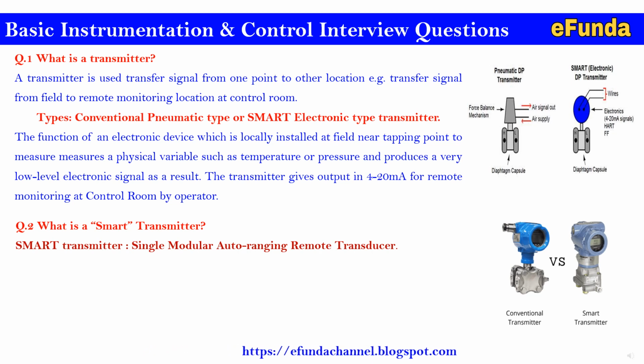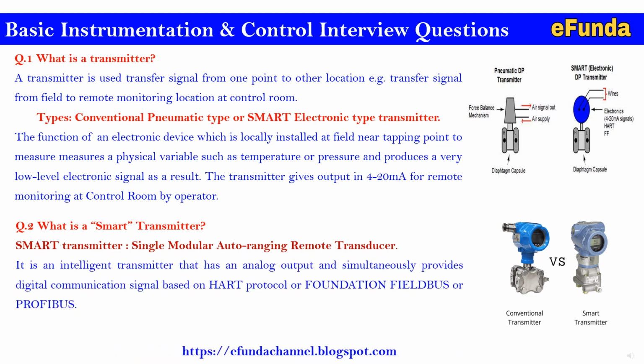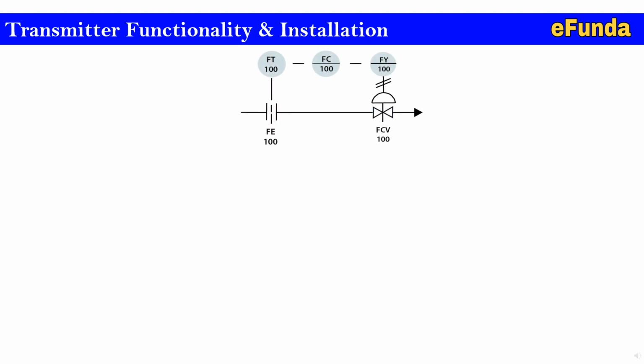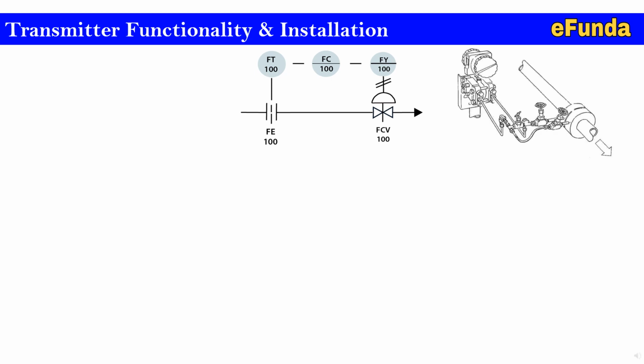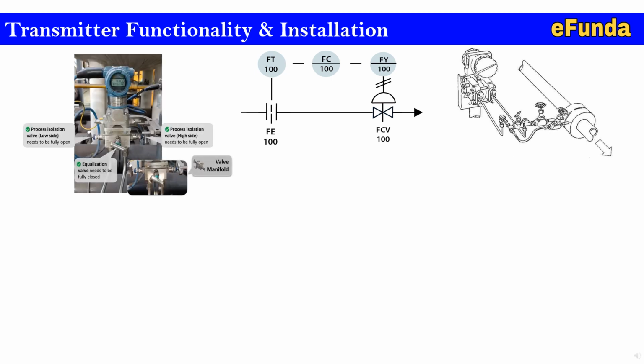One can refer to the pictures where the conventional transmitter and smart transmitters are shown for better understanding. It is an intelligent transmitter that has an analog output and simultaneously provides a digital communication signal, which is based on HART protocol or a Foundation Fieldbus or a Profibus for diagnostic purposes. Transmitter functionality and installation. One can refer to the closed loop where FE, FT, FC, FY, FCVs are shown, and similarly one can refer to the other figure where typically a transmitter is installed with the help of a tapping stanchion or a mounting stand so as to have the correct installation of a transmitter at the field location. Simultaneously, one can refer to the picture where the exact installation of a transmitter is shown in the field.